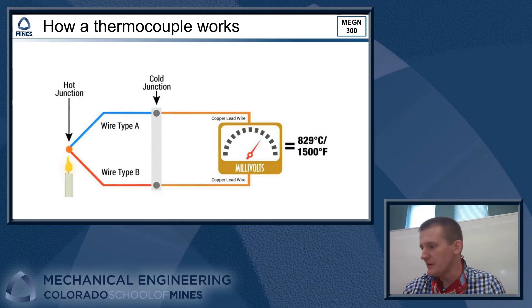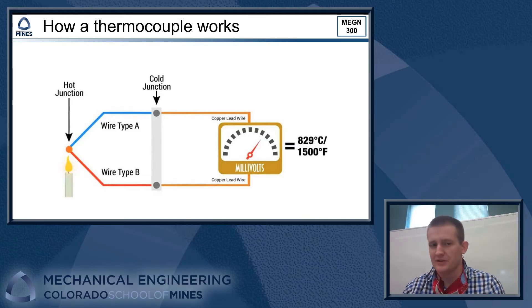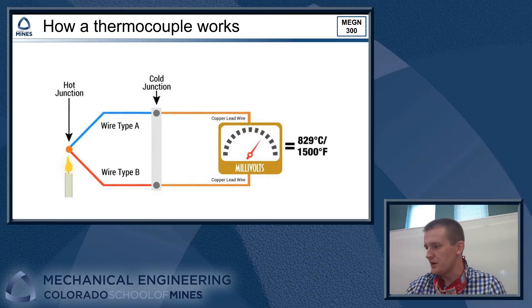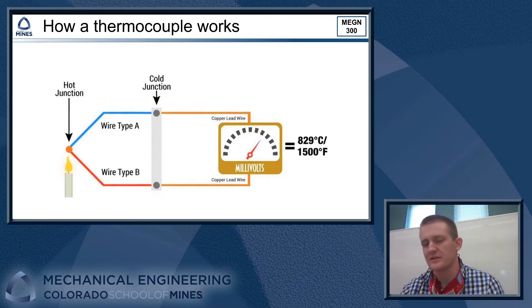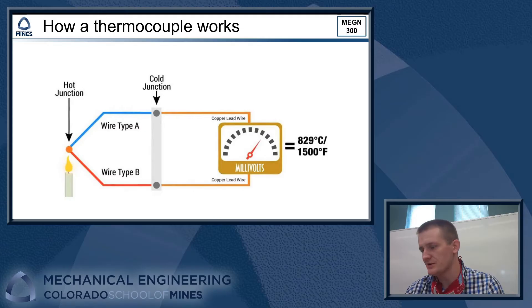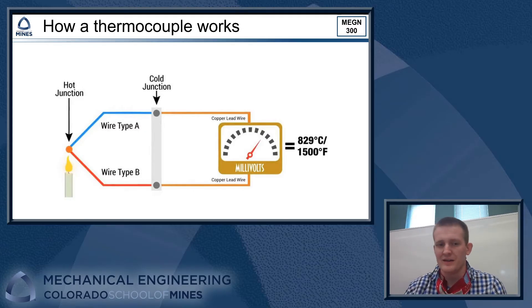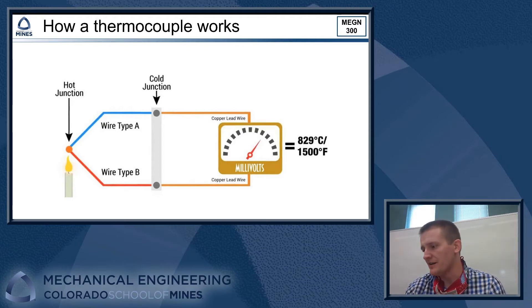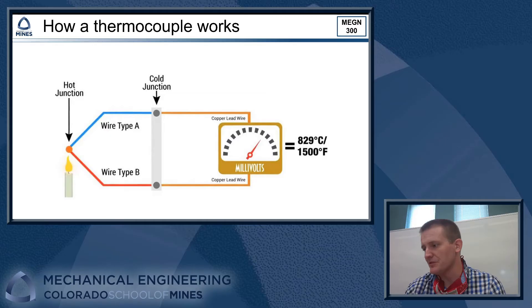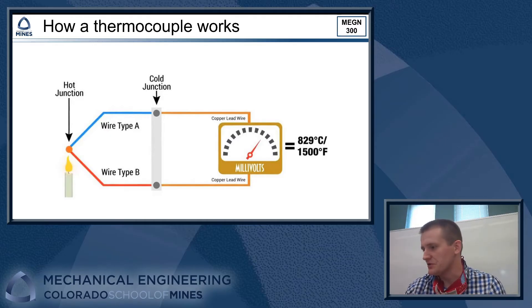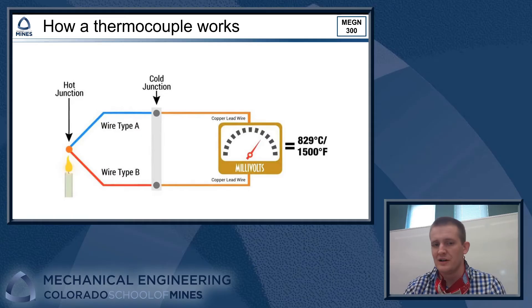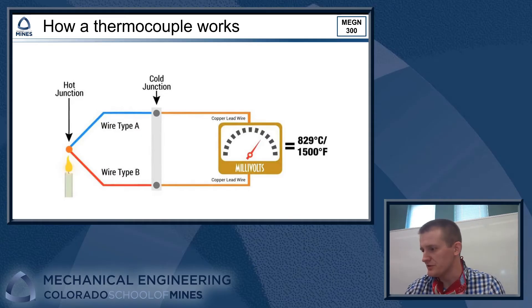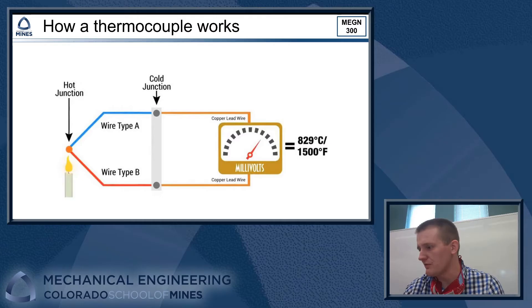The one thing to keep in mind here also that's going to show up in LabVIEW is you'll notice we have the cold junction labeled here because we do have our wires that are joining to a different alloy again. The thermocouple has its own special alloys that are inside of it, and then typically we're connecting to some copper wires inside of our instrumentation system. That junction where we go from the thermocouple alloys to the copper wires is another dissimilar metal junction where we're going to get a voltage potential. So it's important for us to know the temperature of this cold junction. There's a factor that we call the cold junction correction that we're going to be setting in LabVIEW when we set this up.